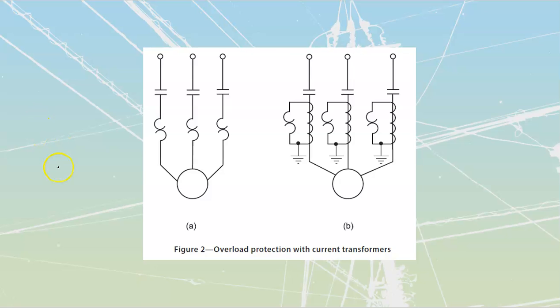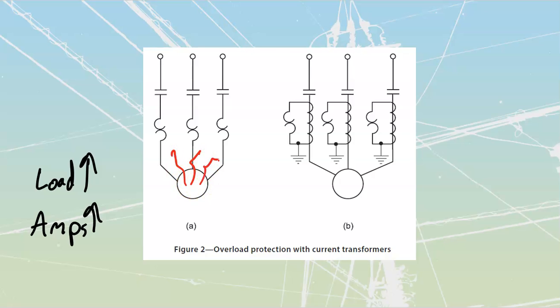You're going to find out that as my load goes up on the motor, my amps are going to go up on the motor. And if my amps go up on the motor, that could lead to burnout on the motor itself, because we're going to have I squared R. We're going to have heat. So we're going to want to monitor the amount of amps going in. Now, we don't want to place fancy metering circuits inside this. So what we've done is we've created these things called overloads.